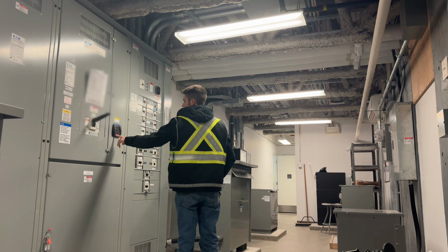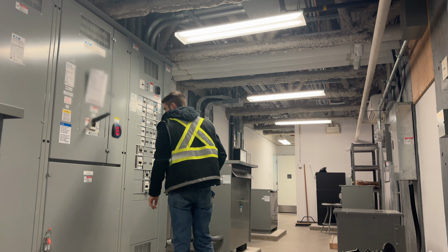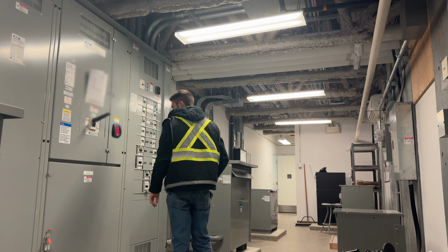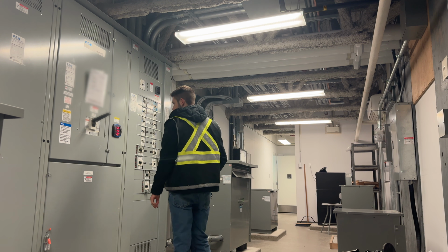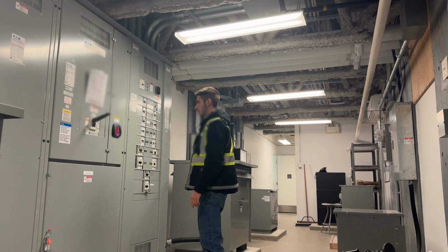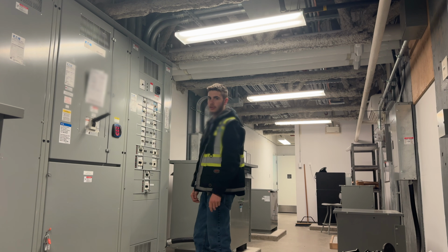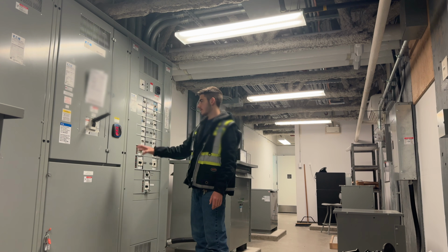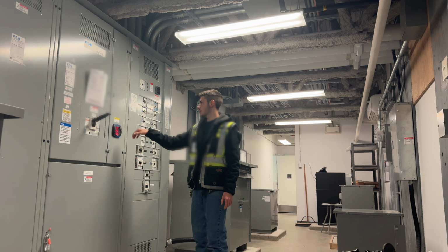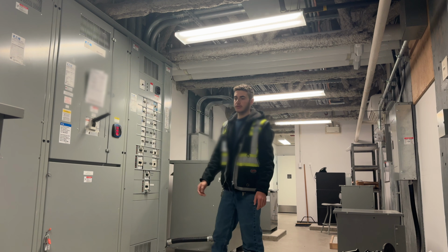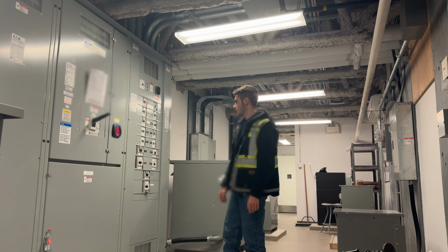Our load on our main service is super low today. A phase 153 amps, B phase 164 amps, C phase 128 amps. Remember too, 20 or 25-ish amps of that are on the generator. There would be 25 more amps on our main service if we weren't on generator power.